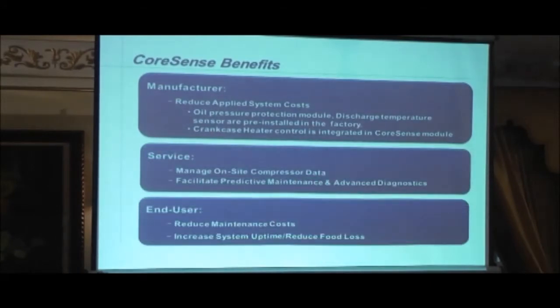So what are the benefits? We have a reduction in applied system costs, because all these accessories which we're going to be supplying as standard are already pre-wired in the factory for you. Okay, you do not have to go and source these components in the market. In terms of serviceability, the technician can now access the complete history of the compressor. That will help him diagnose any problems in the system. And for the end user, if he's connected this to a network, he can keep a record of whenever the compressor went down and what kind of maintenance was done on the compressor to get it back into operation. So those are the main benefits for the diagnostics.